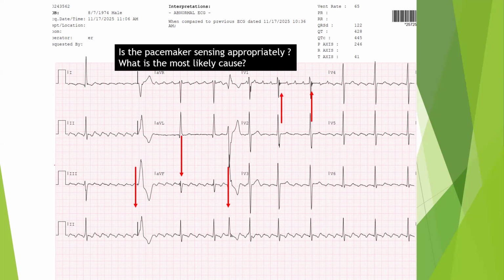Okay, and you need to do a few maneuvers to make sure that the integrity of the lead is okay as well. So with the programmer and ECG machine present, you check the impedance, and the change in impedance if the patient moves his arm, and whether there is noise detected by the programmer when the patient is, for example, pushing against resistance with his left arm. After checking that the lead is functioning well from the lead point of view, with no sign of lead fracture or insulator break, and checking by X-ray that the lead is not displaced too much, then the default is to try to program around it.